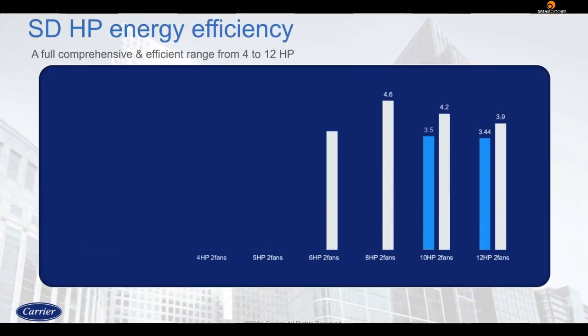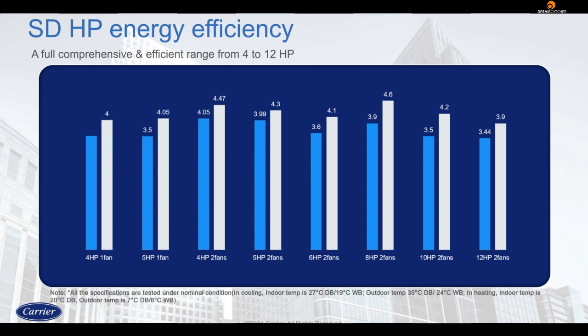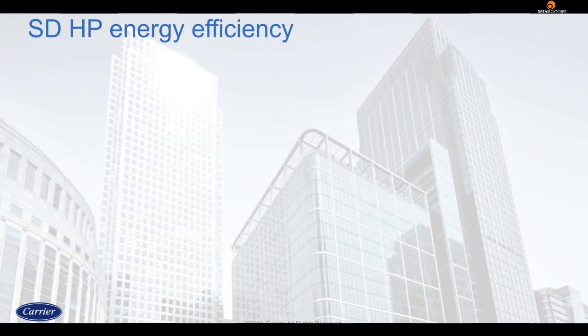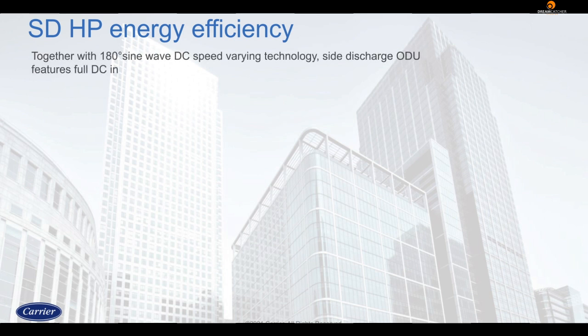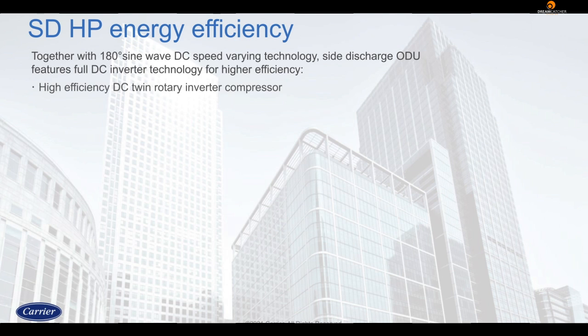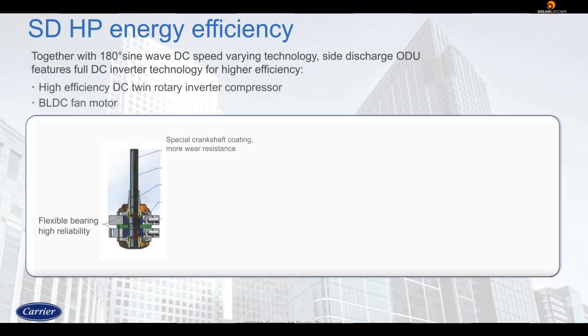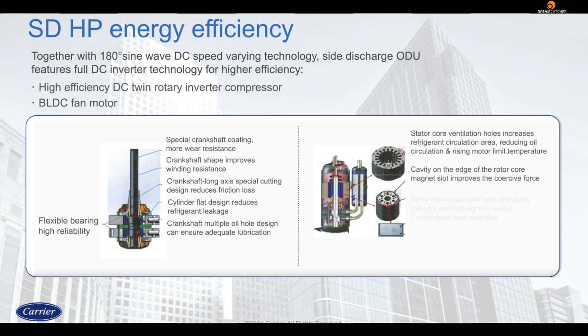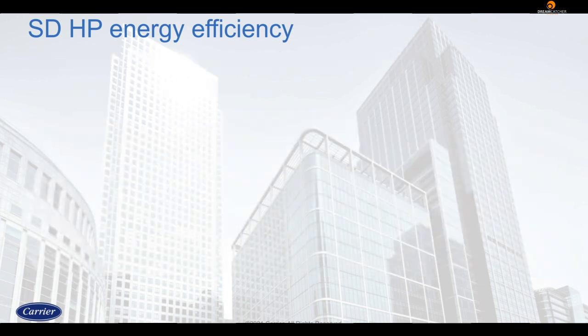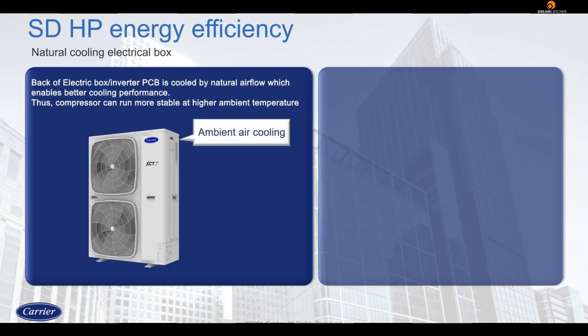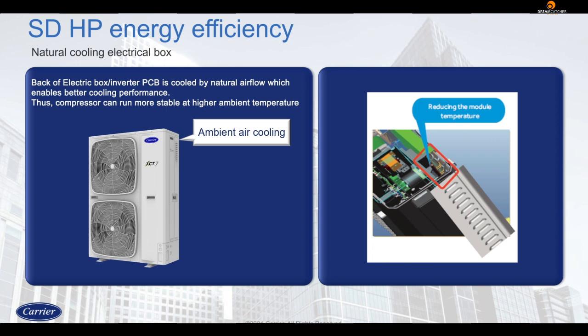The side discharge units offer very stable efficiency across capacities for both single and double fan units. With the 180-degree sine wave DC speed varying technology, the side discharge system offers full DC inverter technology, along with DC twin rotary inverter compressor and BLDC fan motors for higher efficiency. The efficiency is further increased by a natural cooling electrical box, where the back of the electrical box or the inverter PCB is cooled by natural airflow through grills, allowing it to run with more stability.